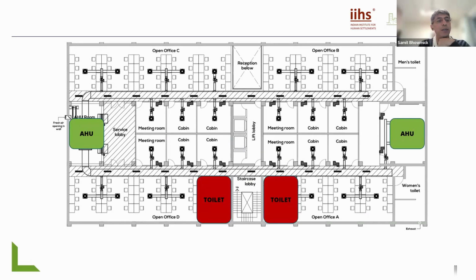You have an office space, you're trying to get outdoor air in, the air handling units bring outdoor air into the space, and you can only do it till the space is full. Unless we start extracting air from that space, we cannot get fresh air in. So if we want to achieve a certain indoor air quality, or get a certain amount of fresh air into the space for a healthy environment, the extraction needs to be matched to it. If that's not done, the ideas only remain on paper, and you'll only be able to get into the building as much as you can extract.